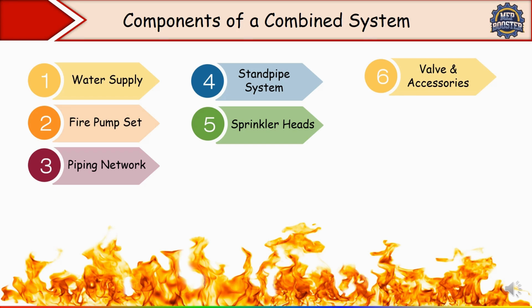Then valves and accessories. Okay, so different types of valves we are using. Alarm valve, which activates alarm when water flows. Then we have a pressure relief valve, which prevents excess pressure buildup. Flow switch also we are using, which sends a signal to the fire alarm control panel. Then control valve normally isolates section for maintenance. Okay, so different types of valves and accessories are there.